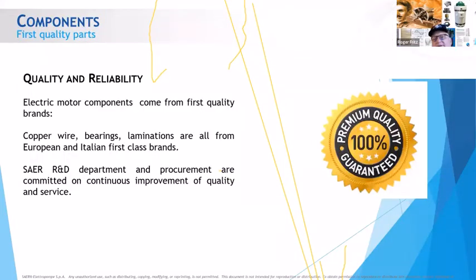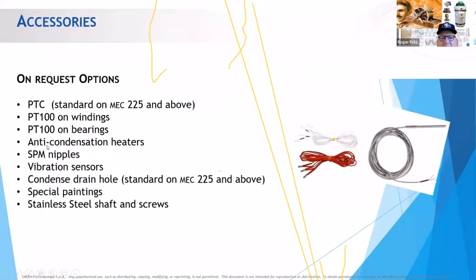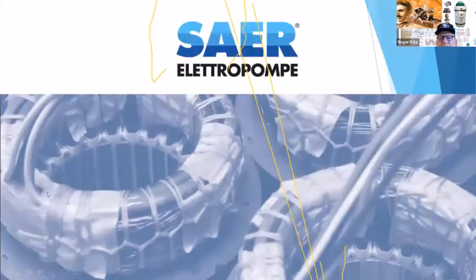And also, the design and the quality of the copper wire, the bearings, the laminations. I'm involved a little bit with SAER, and they are very critical to the design of their motors and to the proper copper wire, bearing types, laminations and materials. Even the different types of windings that are available. They also build in heaters, vibration sensors, special paint.